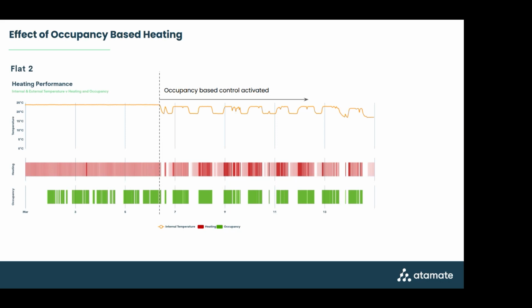So we use the PIR, which is instantaneous, to turn things on, and then we use the decay in CO2 to decide the room's unoccupied. That's the occupancy at the bottom. Then we've got the heating as this red band, and the temperatures above. Before the dotted line, the temperature is just being held constant - this electric heater is just being turned on and off to keep that temperature constant. After this line, straight away we go into occupancy-based controls, allowing the temperature to drop back when there's no occupancy in the space. It's pretty obvious - it's relatively easy to start saving energy and saving money with that.